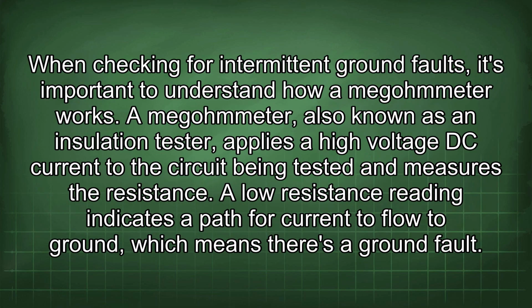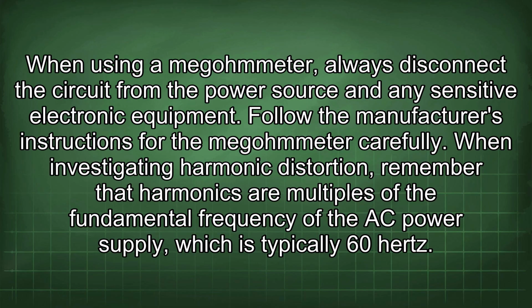When checking for intermittent ground faults, it's important to understand how a megohmmeter works. A megohmmeter, also known as an insulation tester, applies a high voltage DC current to the circuit being tested and measures the resistance. A low resistance reading indicates a path for current to flow to ground, which means there is a ground fault. When using a megohmmeter, always disconnect the circuit from the power source and any sensitive electronic equipment. Follow the manufacturer's instructions for the megohmmeter carefully.